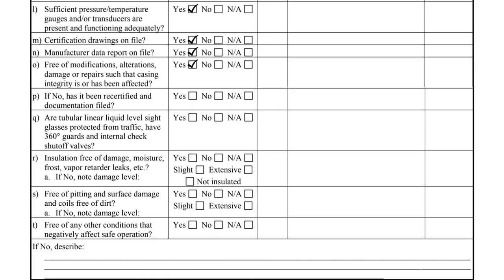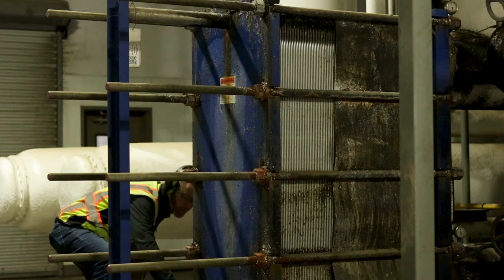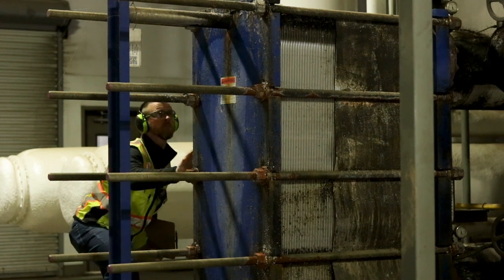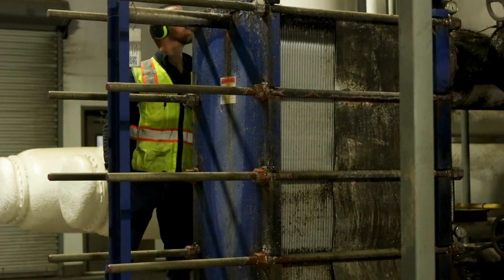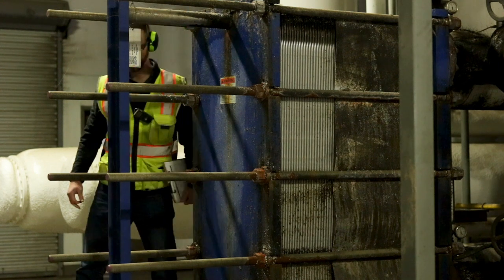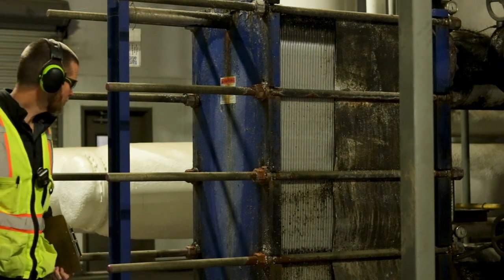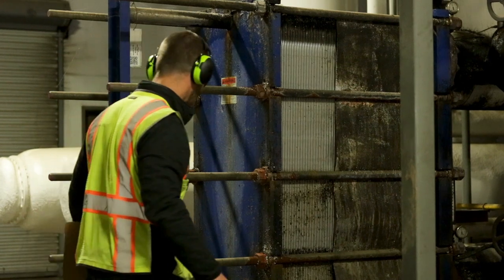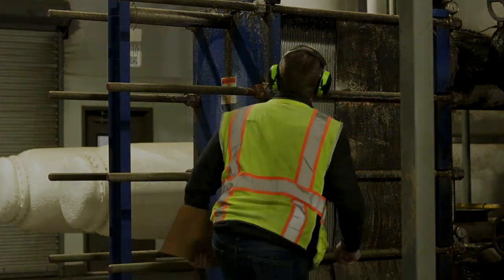Item O asks the inspector if the heat exchanger is free from modifications. While this cannot be conclusively answered in the absence of a data report, the inspector can still look for indications that alterations have occurred. If there is evidence of equipment modifications, the appropriate checkbox in Item P must be answered.